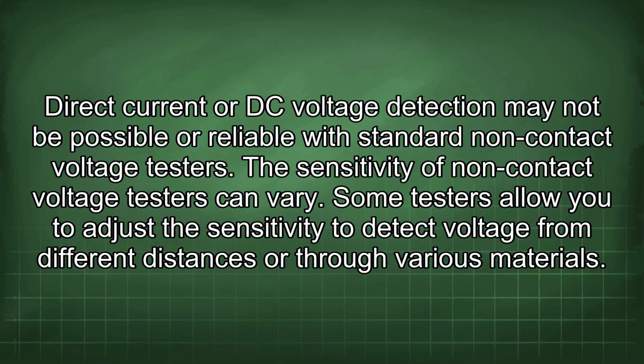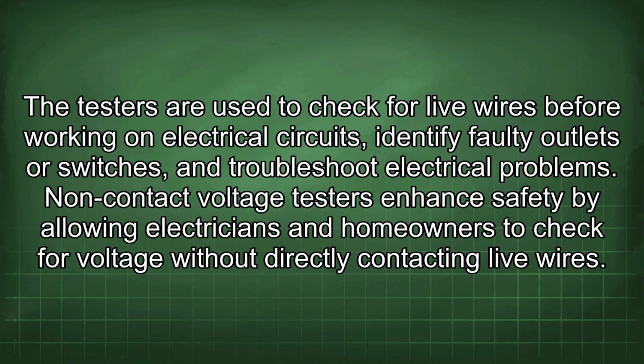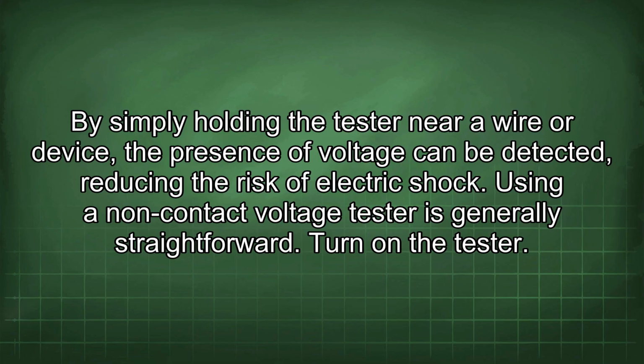The sensitivity of non-contact voltage testers can vary. Some testers allow you to adjust the sensitivity to detect voltage from different distances or through various materials. The testers are used to check for live wires before working on electrical circuits, identify faulty outlets or switches, and troubleshoot electrical problems. Non-contact voltage testers enhance safety by allowing electricians and homeowners to check for voltage without directly contacting live wires. By simply holding the tester near a wire or device, the presence of voltage can be detected, reducing the risk of electric shock.